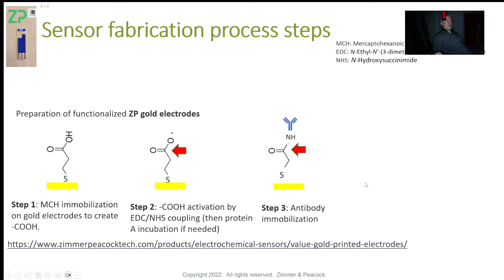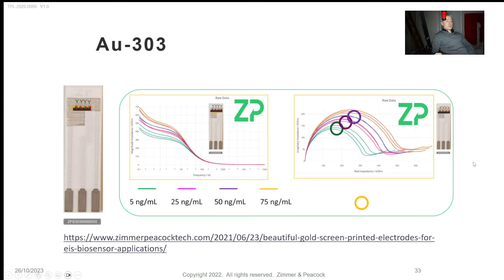We do use impedance spectroscopy quite a bit. Here's our link. And this is a protein sensor, and it does work really quite well. Something I'm going to touch upon in a minute. The only reason we're able to make such progress on many of the sensors that we do is that most of our revenue is from contract development and contract manufacturing. The only reason we're able to make such good progress is because the electrodes are fundamentally reproducible. Here we've got three electrodes tested at 5 nanograms per mil, 3 electrodes tested at 25 nanograms per mil, 3 electrodes tested at 50 nanograms per mil, 3 electrodes tested at 75 nanograms per mil. And it's because of the skill of the people in the laboratories, but also the quality of the underlying electrodes.